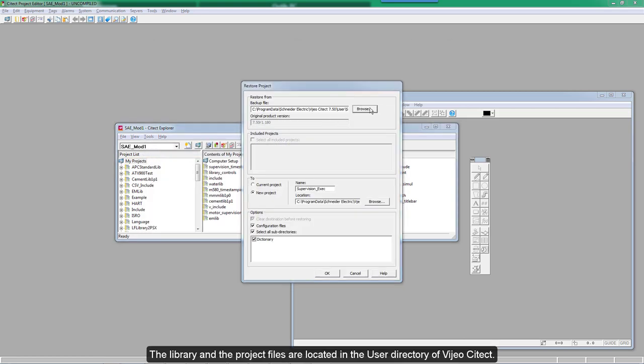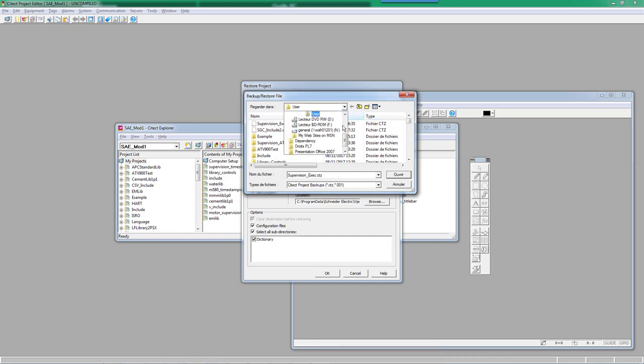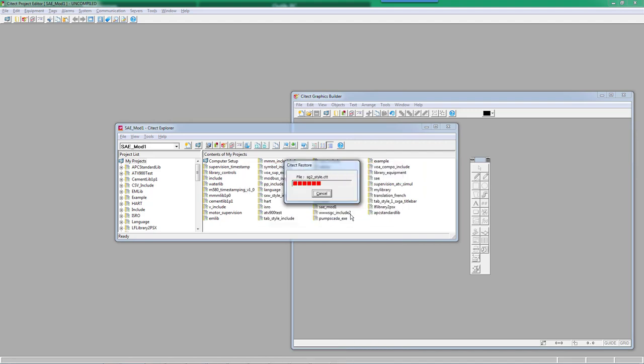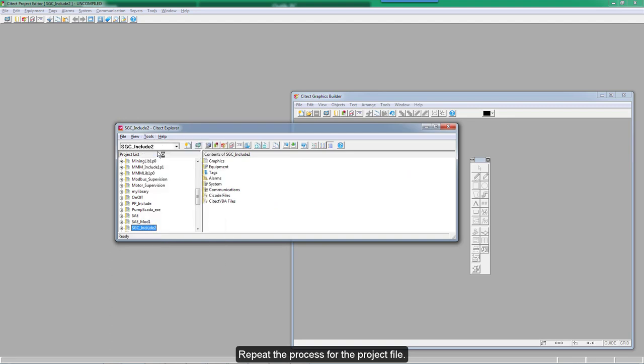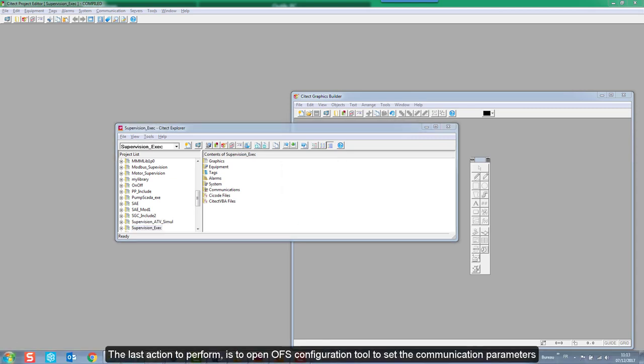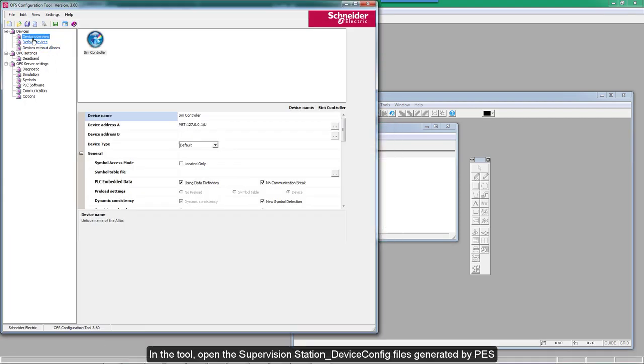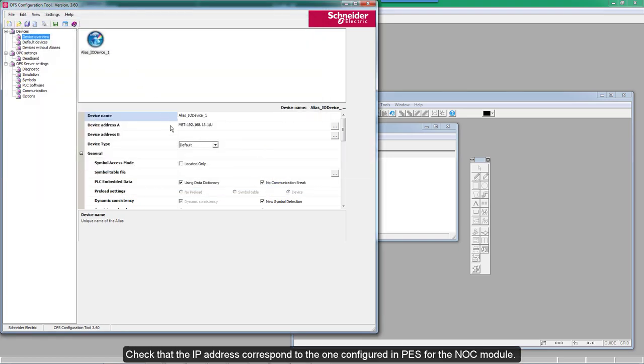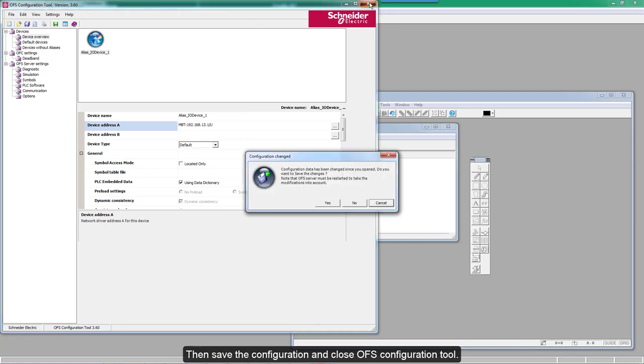The library and the project files are located in the user directory of Vijeo Citect. Browse from the Program Data folder up to the user directory. Select the library file and restore it. Repeat the process for the project file. The last action to perform is to open the OFS Configuration tool to set the communication parameters. In the tool, open the supervision station device config files generated by PES. This file is in the OFS directory available from the Program Data folder. Check that the IP address corresponds to the one configured in PES for the NOC module, then save the configuration and close the OFS Configuration tool.